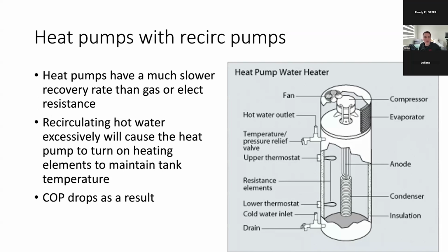But the problem with heat pumps is that they generally do not like recirculation pumps. A lot of the manufacturers are saying that if you're combining a recirculation system with a heat pump water heater, you need to either have it on electric resistance mode, which basically turns on these little heating elements, and then you lose all of your efficiency from the heat pump, or you have to have an on-demand control. Recirculating hot water excessively in a heat pump is going to diminish the heating capacity as well as the coefficient of performance.